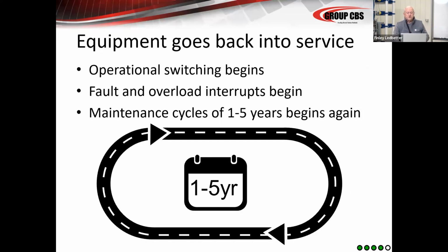It goes back into service, and here you go again on this racetrack. Every 5 years, you're going to test it. So now it's 55 years, 60 years, 65, 70, and 75 years. You're going to do the same maintenance: test, inspect, clean, lube, and adjust on these mechanisms. You're going to do a lot of timing tests that you didn't do in the early years, to ensure your breakers are operating at speed and velocity. And you're going to make sure you change that lube because they don't like staying closed like this for 50 years, right?